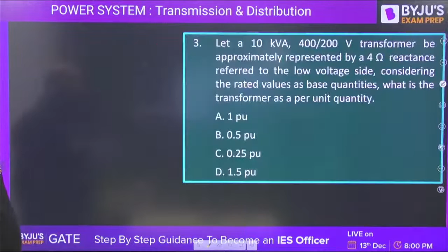Let a 10 kVA 400/200 volts transformer be approximately represented by a 4 ohm reactance referred to the low voltage side, that is the 200 volts. Considering the rated values as base quantities, what is the transformer impedance as a per unit quantity? Now you know.